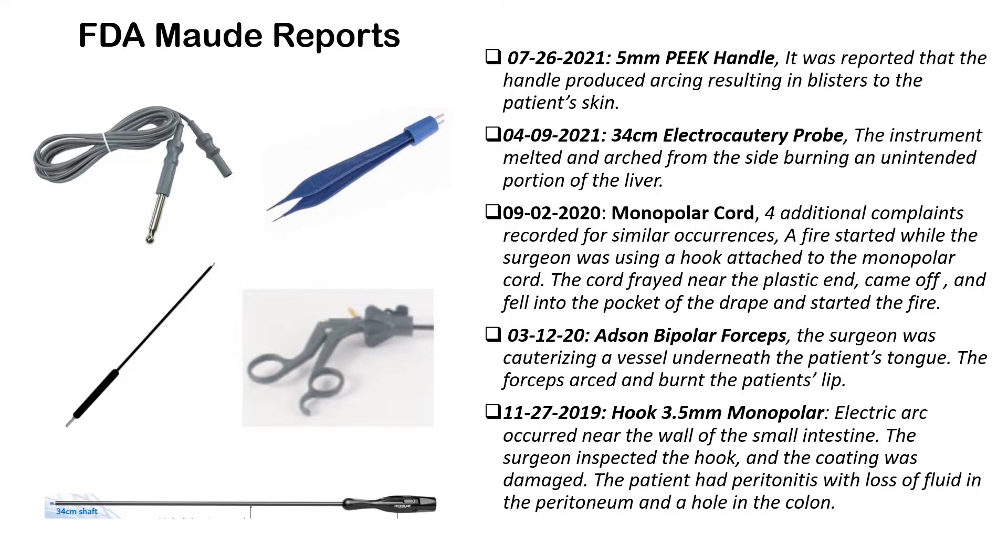In March of 2020, Adson bipolar forceps — the surgeon was cauterizing a vessel underneath the patient's tongue — the forceps arced and burned the patient's lip. In November of 2019, a monopolar hook electric arc occurred near the wall of the small intestine. The surgeon inspected the hook and the coating was damaged. The patient had peritonitis with a loss of fluid in the peritoneum and a hole in the colon.